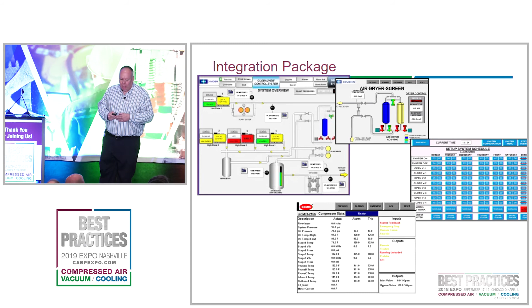And then what I call a full integration package is one that actually has to talk to your compressor. It has to be a compressor with an open protocol that allows it to speak to the system and read all the data, especially with centrifugal compressors, where you get vibrations, amp draws, temperatures, and everything critical to those machines. You can trend those over time, and since these are typically more expensive investments, it affords you more leeway in purchasing equipment to support that.